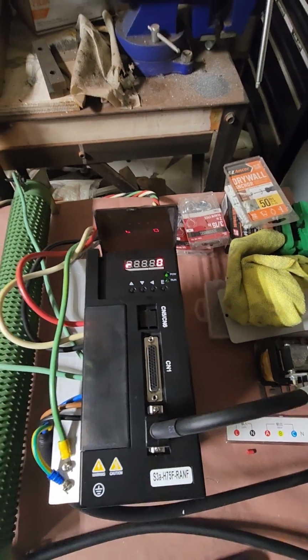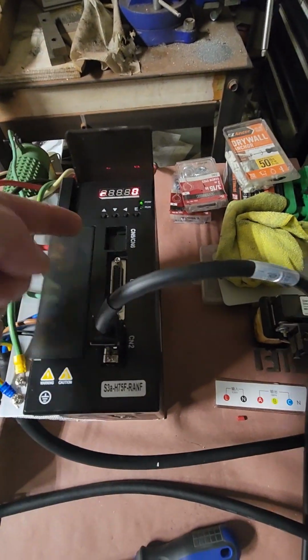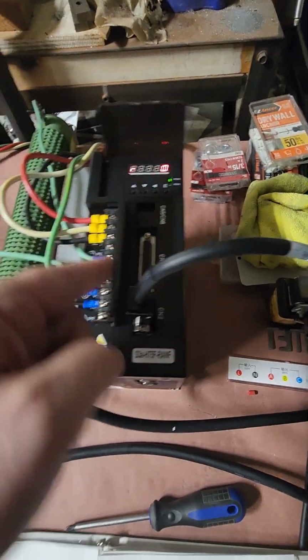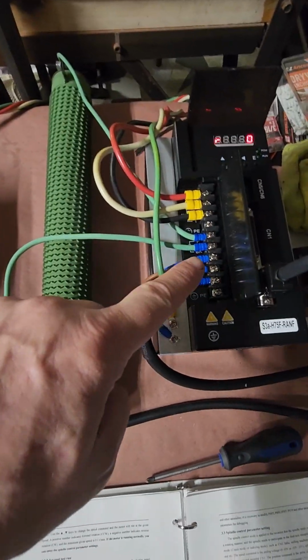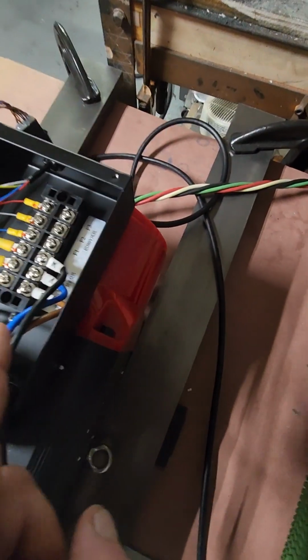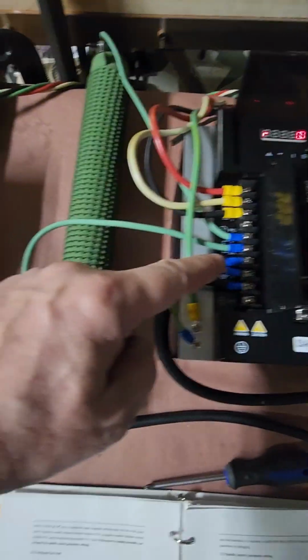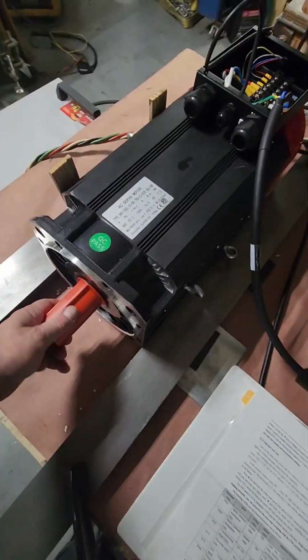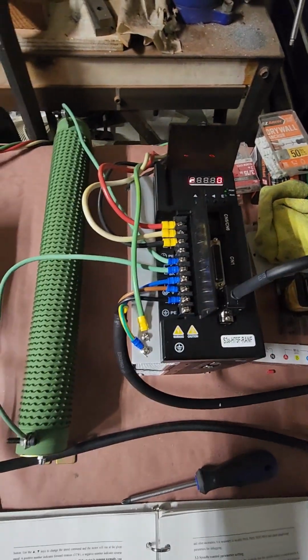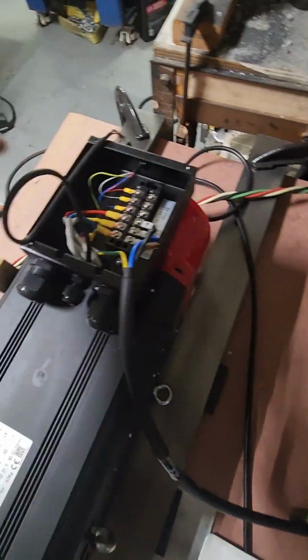So I need to enable it. One thing I observed, these suckers wired the terminals on the motor wrong. I had it correctly wired here. You see U, V, W — that's how they were, U, V, W, and it was spinning like crazy. I flipped U and V, and now it's working correctly. So it came from the factory with the wires wrongly connected.